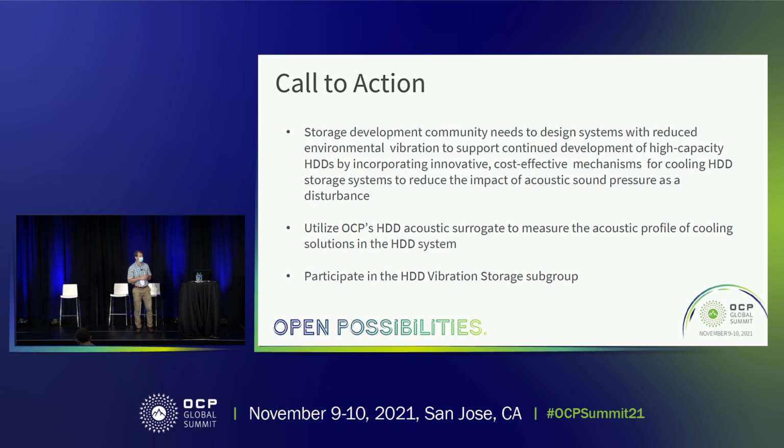Matt Shumway was talking about it before, and if you go to the Expo Center on the experience side, they have the OCP storage surrogate. There's an HDD surrogate with 2 microphones on it. You can put it in your rear slots in an enclosure, and it can provide an estimate of how well it's going to do as we increase the number of tracks per inch in these drives. As it gets more and more dense, you can get an idea of how well your system is doing acoustically. That's all it's really checking at that time. And then I'm encouraging everyone to get involved in the vibration storage subgroup.